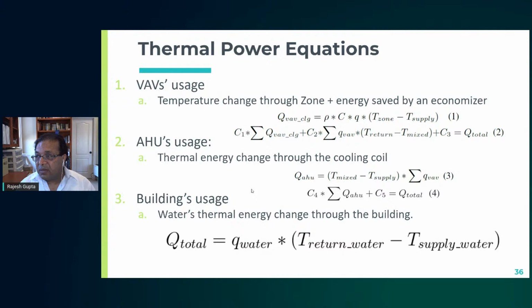So you can then write up the equations that measure the temperature, measure the airflow, and then based on that compute how much energy is being extracted or inserted into a given zone, and then you add them up as a total energy usage. And the energy usage could be because of the change in water temperature versus change in the air temperature.